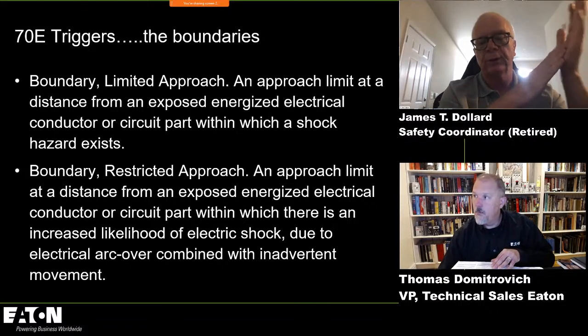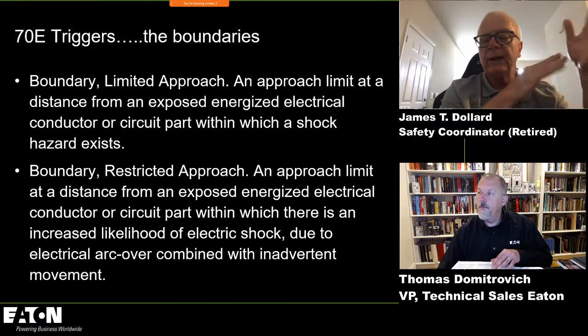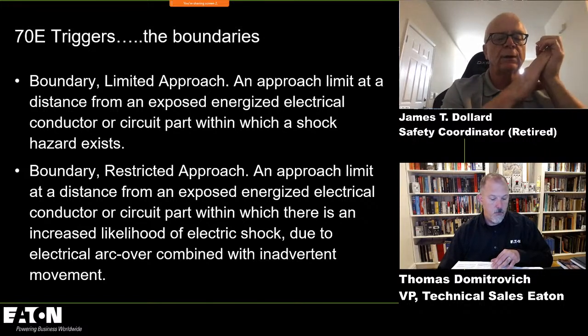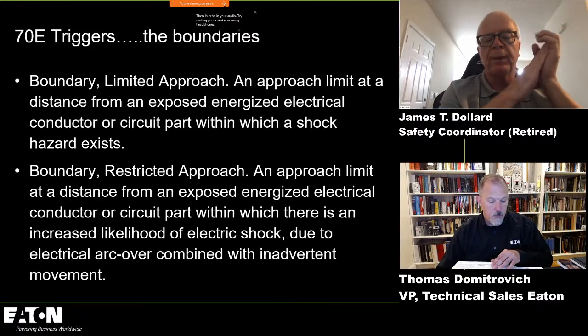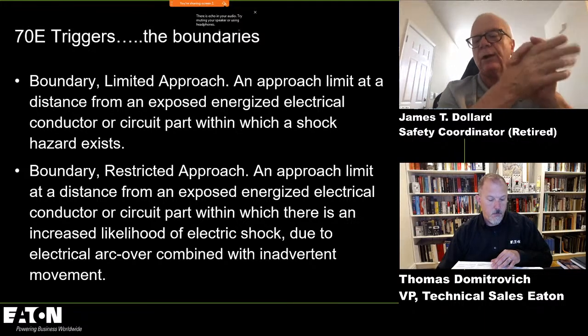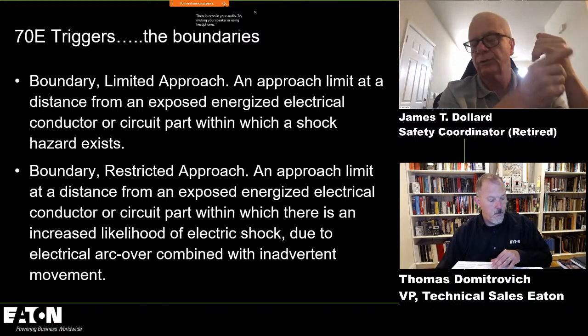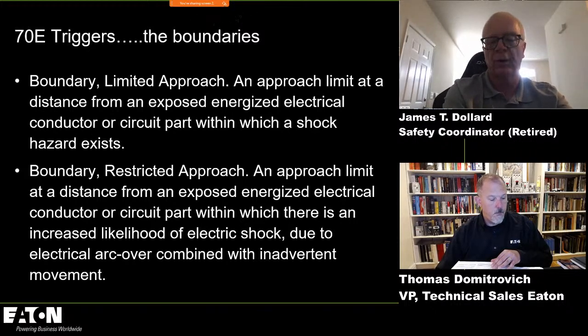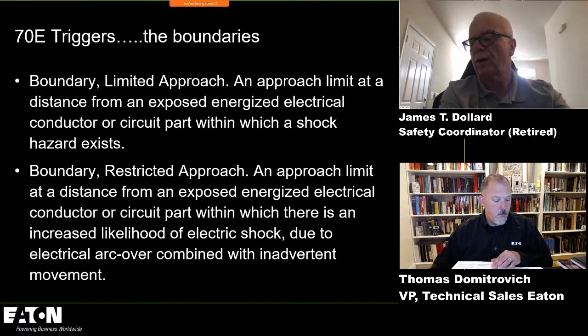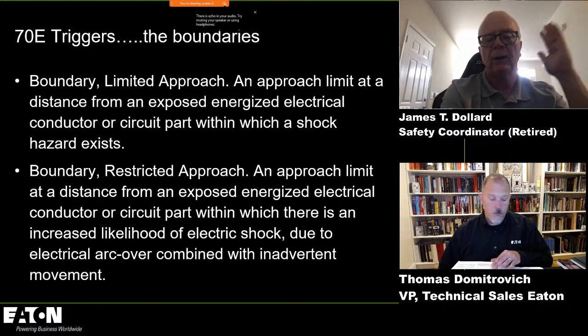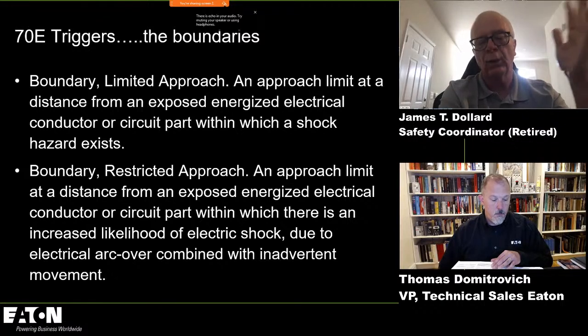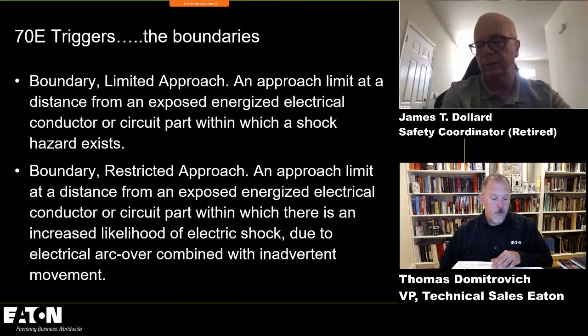With restricted approach, that's a distance where there's an increased likelihood of electric shock due to arc over combined with inadvertent movement. That starts at 151 volts and goes to 750 volts. And that's 1 foot. And that's a trigger. So for the limited approach boundary, the trigger is that only qualified persons cross that boundary. For the restricted approach boundary, if we have to cross it, we have to be wearing rubber insulating gloves and leather protectors. If we're using a tool, it has to be insulated inside the restricted approach boundary.